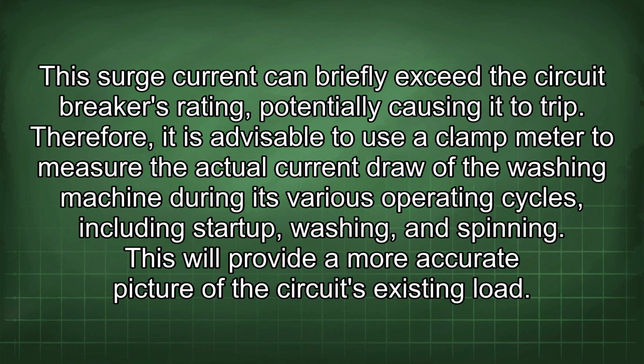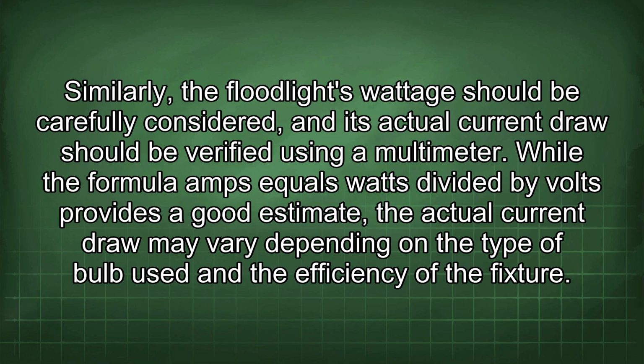Therefore, it is advisable to use a clamp meter to measure the actual current draw of the washing machine during its various operating cycles, including startup, washing, and spinning. This will provide a more accurate picture of the circuit's existing load. Similarly, the floodlight's wattage should be carefully considered, and its actual current draw should be verified using a multimeter. While the formula amps equals watts divided by volts provides a good estimate, the actual current draw may vary depending on the type of bulb used and the efficiency of the fixture.